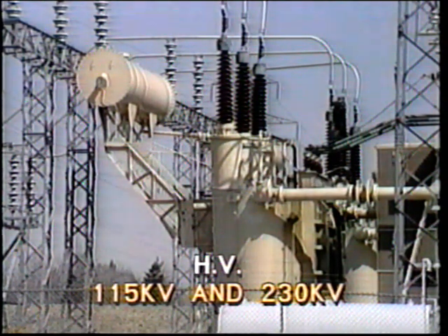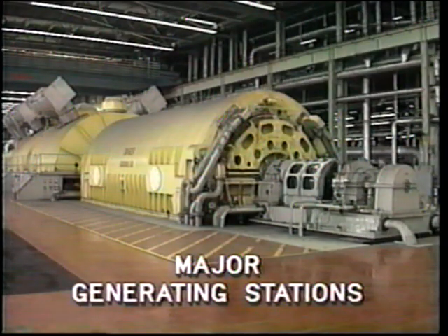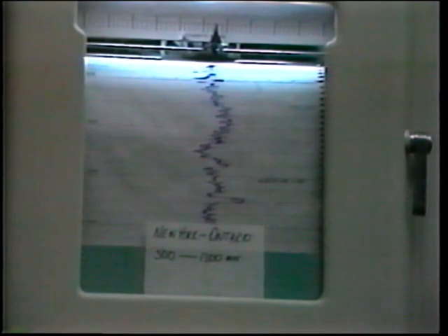This allows at least one end of each high voltage line to be monitored. Every major generating station, and every station with interconnections to other systems. Normally, oscillographs are not located at the distribution substations except those installed to analyze special problems or to conduct research.